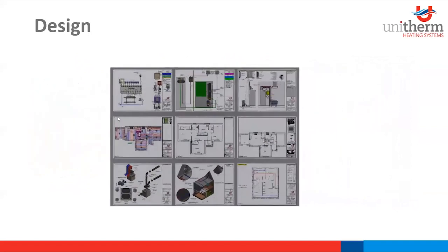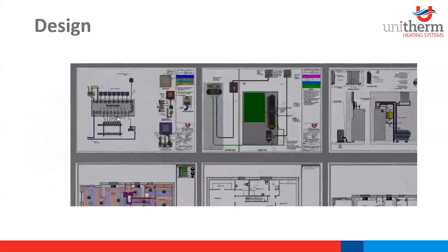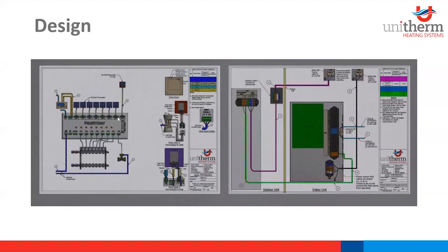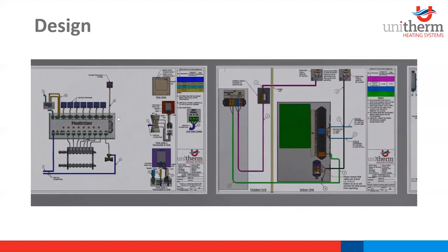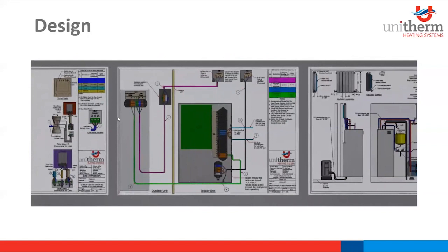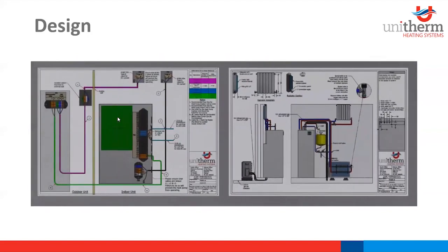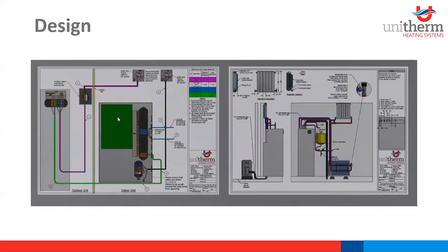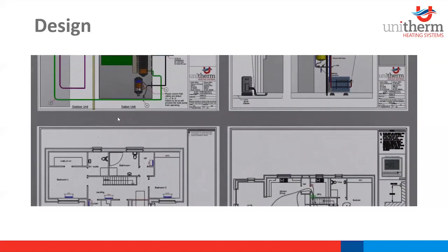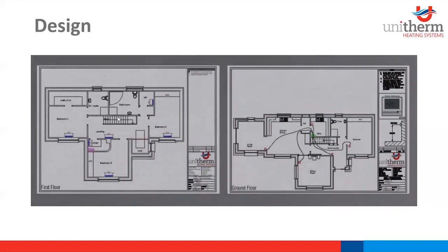From the drawings, with integration of mechanical and electrical components, we have wiring centres, stats, actuators, PLC controllers. We supply first and second fix mechanical and electrical drawings with cable sizes and pipe sizes required for each individual system and heat pump.